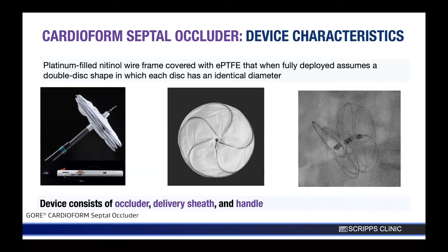The device itself actually consists of the occluder, the delivery sheath, and the handle, which comes as a set. So you do not need a separate sheath or delivery system for this. It all comes as one in the box. All right, so what are the properties of the Cardioform septal occluder? And this is where I think it differentiates itself. First, the ePTFE is known to have low thrombogenicity and a minimal inflammatory response, which leads to rapid endothelialization. You see here just an example in the 30-day canine model of the glistening endothelium around this device. And there's a long track record of ePTFE in medical implantable devices, which this device leverages.